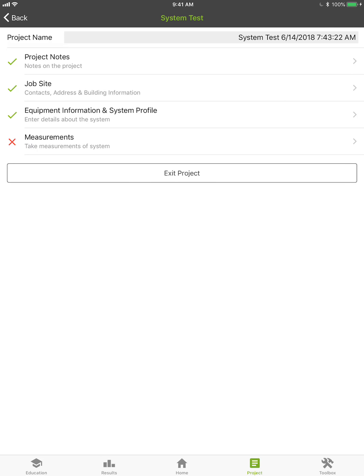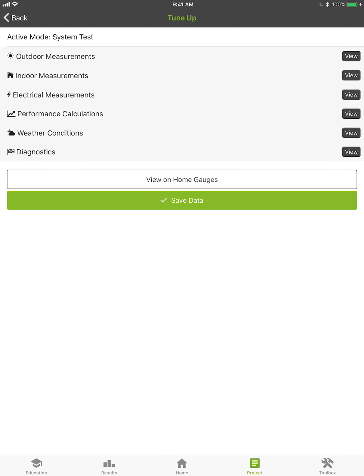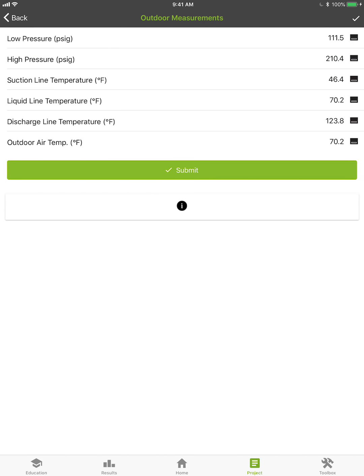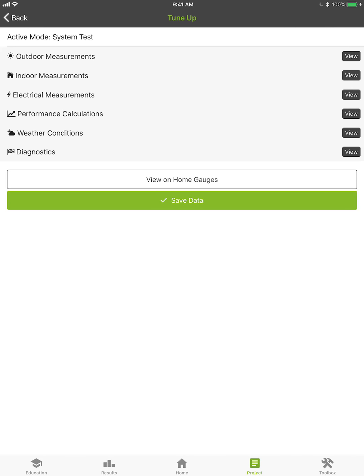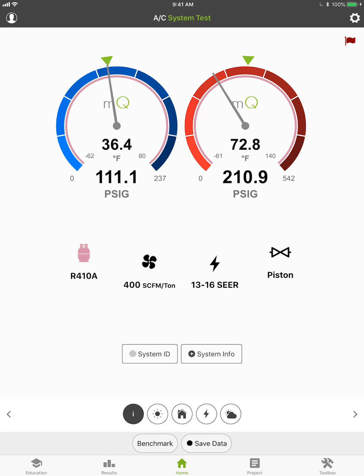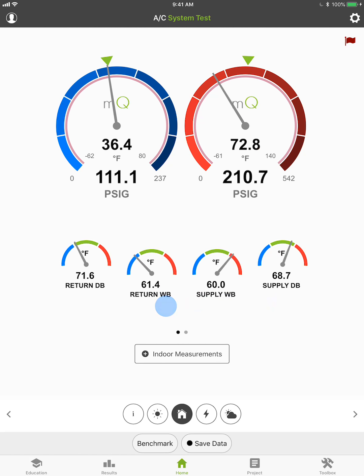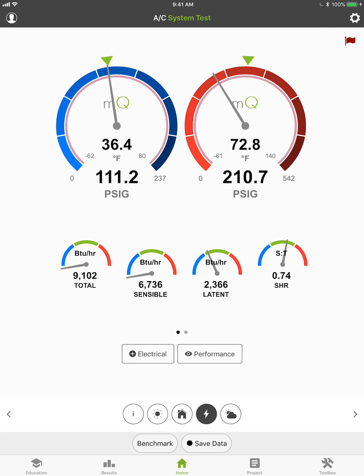Now I'll go into Measurements — this is what's really cool. Once we have this tied in with the cloud, all I'd have to do is come out, select the pin and unit I'm working on, and go right into measurements because all the project, job site, and equipment information is already entered. There are two ways to view measurements: click the View button to look at any of the subsets with live data coming in. The black box icon next to readings indicates an iConnect, so we know the data source. I can also view on the home screen gauges for a different UI where I can scroll through superheat, subcooling, suction line, and all the data.